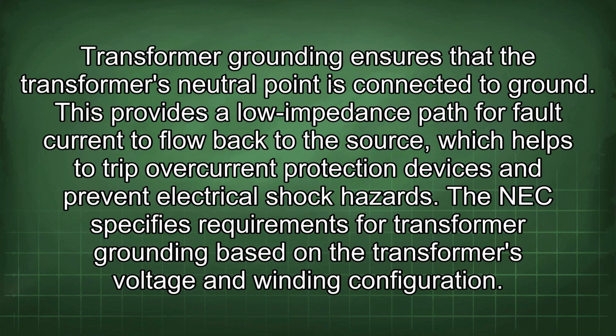Transformer grounding ensures that the transformer's neutral point is connected to ground. This provides a low impedance path for fault current to flow back to the source, which helps to trip overcurrent protection devices and prevent electrical shock hazards. The NEC specifies requirements for transformer grounding based on the transformer's voltage and winding configuration.